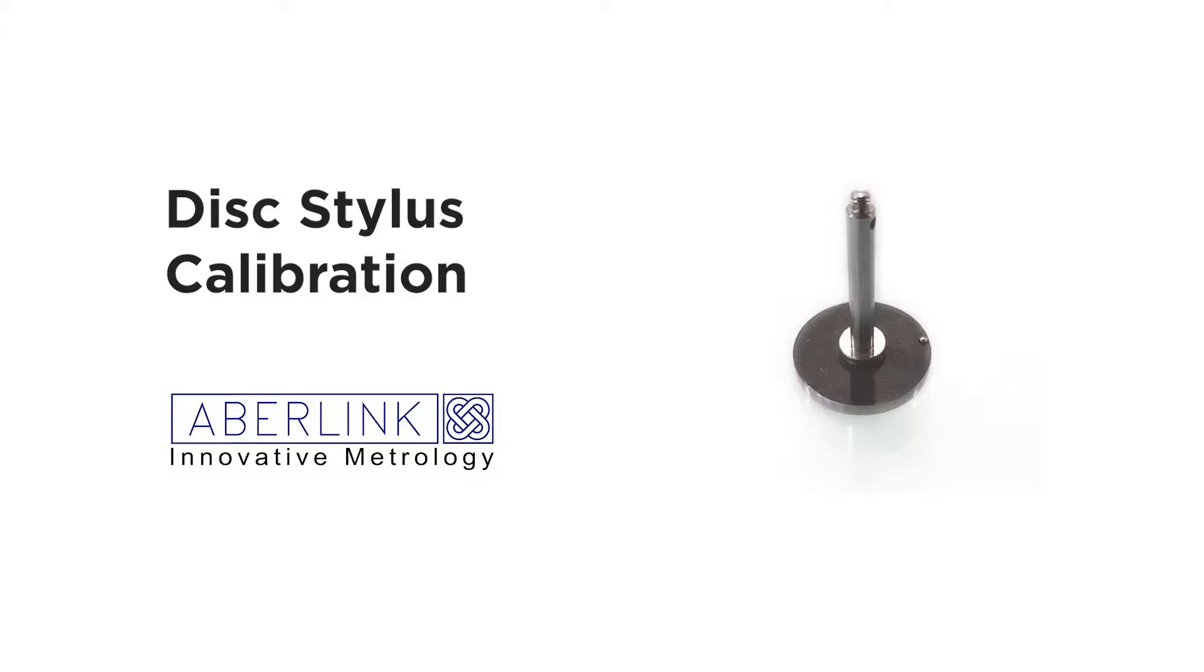The information we need to know before we start is the diameter of the disc, also the length of the stud, and you can do this with a vernier or a micrometer, and also how far away the stud is from the center of the stylus. This is going to be an offset we need to enter.